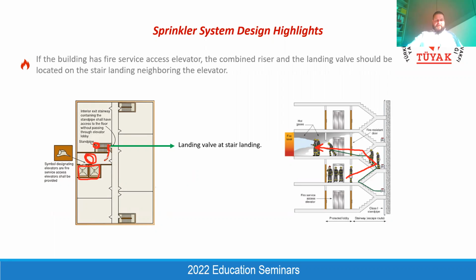For example, if you locate the landing valve in this staircase, first of all, they come with these elevators. They will prepare here, and they will take all of the equipment. They will go to the other stair, and then go to the upper floor to use the landing valve system, and it will cause loss of time for the intervention in the fire. That's why it's always better to have a clear, optimum design, and that's why we are always providing the landing valve in this staircase. It's not taken into account by MEP designers. They are always trying to locate the risers in the nearest staircase, but as an architect, you need to inform them that you require this riser and landing valve in the staircase neighboring the fire service access elevator.